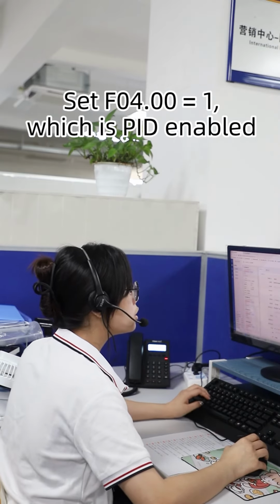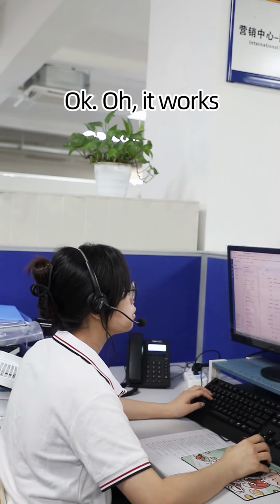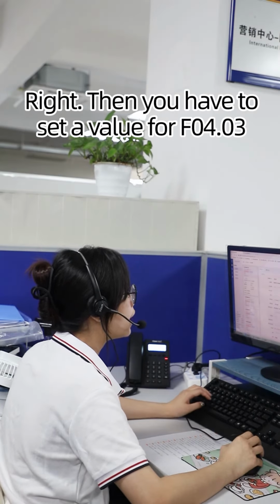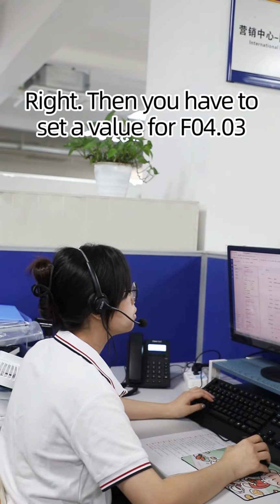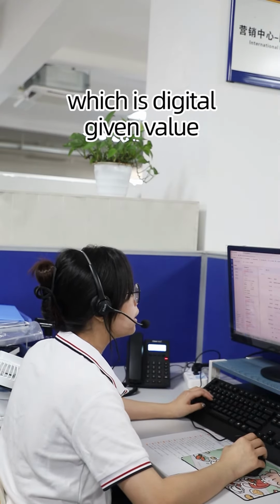F04.00 equals 1, which is PID enabled. Okay. Oh, it works, right? Then you have to set a value for F04.03, which is the digital given value.